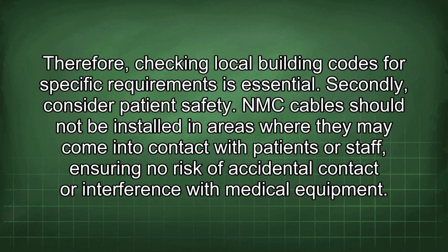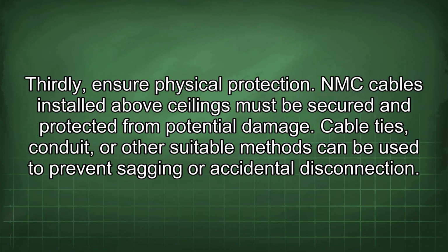Secondly, consider patient safety. NMC cables should not be installed in areas where they may come into contact with patients or staff, ensuring no risk of accidental contact or interference with medical equipment. Thirdly, ensure physical protection. NMC cables installed above ceilings must be secured and protected from potential damage. Cable ties, conduit, or other suitable methods can be used to prevent sagging or accidental disconnection.